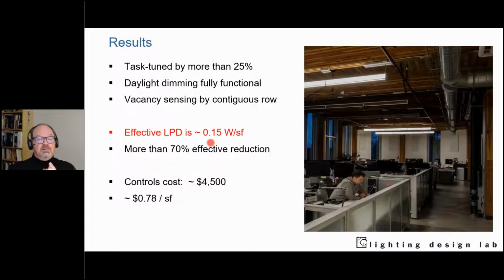From a costing standpoint, this is a retail cost. I found every piece we used on the project and took the retail cost, what it would cost to buy from Amazon, and it came out to about 78 cents per square foot to get this high level control. It used to require $4 to $5 per square foot for this kind of control. Again, that 78 cents is retail; on a project cost basis we'd probably be closer to 50 cents a square foot. I hope this gives people a sense of what's possible, and what's out there with respect to the abilities and effectiveness of these systems.